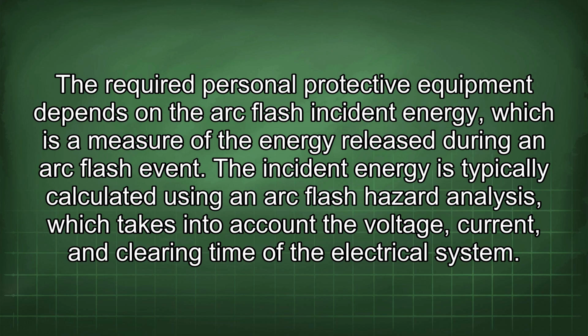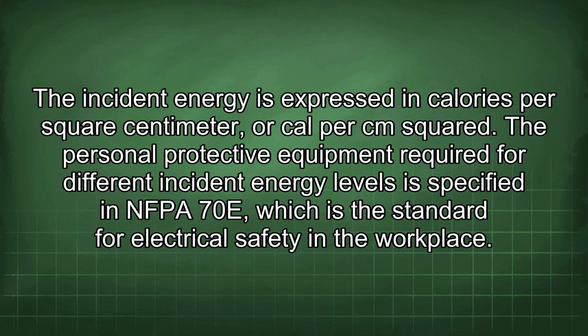The incident energy is typically calculated using an arc flash hazard analysis, which takes into account the voltage, current, and clearing time of the electrical system. The incident energy is expressed in calories per square centimeter, or cal per cm squared.